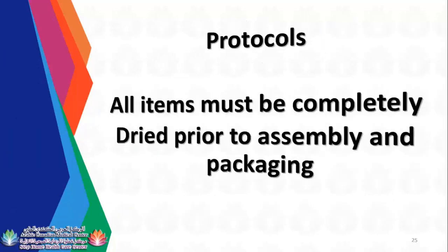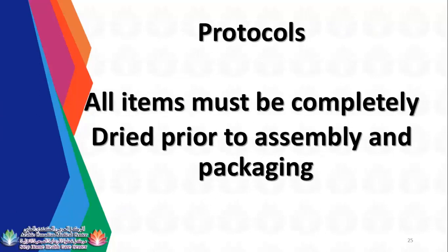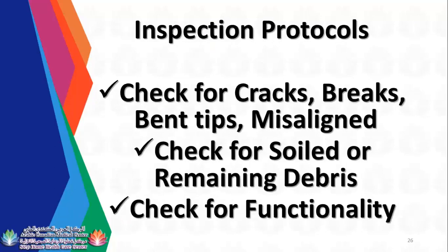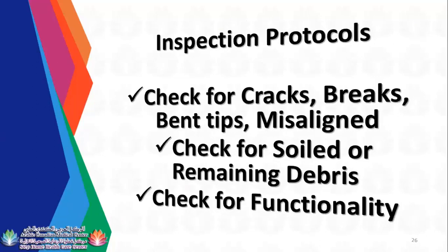And also, the reason why it should be completely dried is because water can interfere with the sterilization cycle and it can damage the integrity of the pouch, especially if you are using paper plastic pouches. Inspection protocols: check for cracks. When you are checking the instruments, you need to check for cracks, and check for breaks. If the bent tips are misaligned, you need to check for soiled or remaining debris, and still check for functionality. So that's your inspection protocols before you close your pouch.